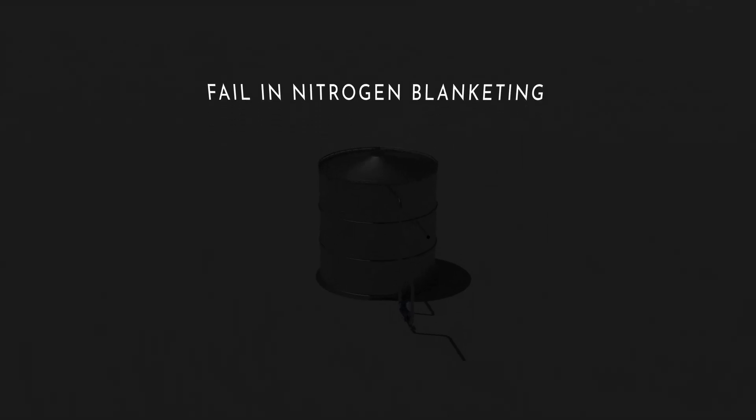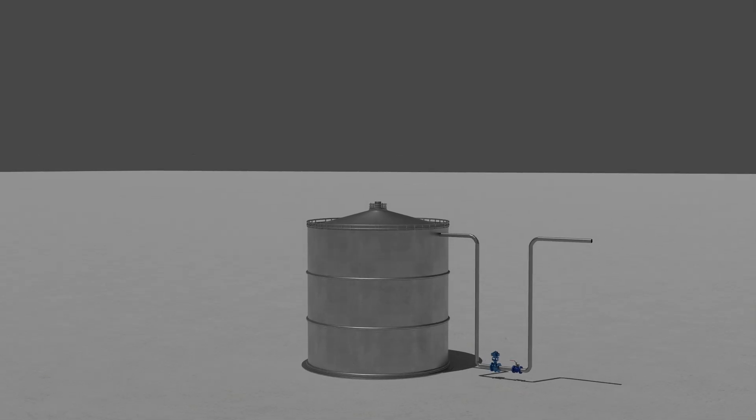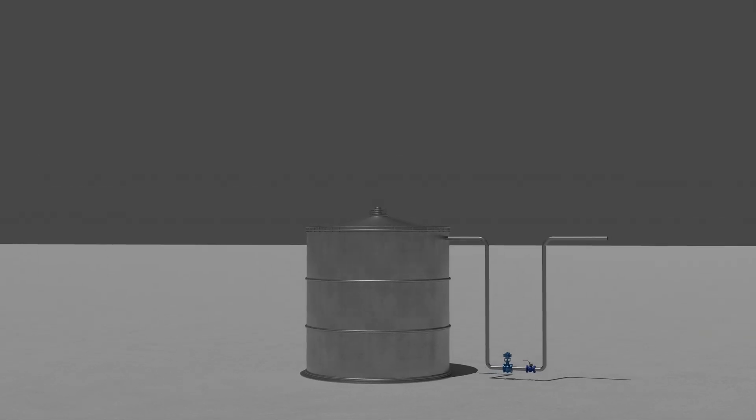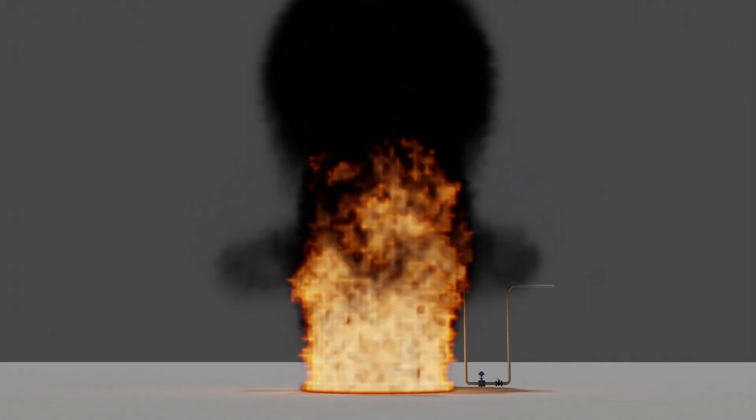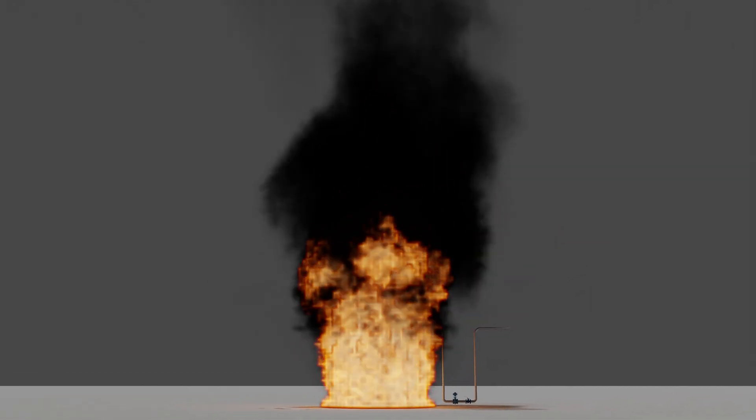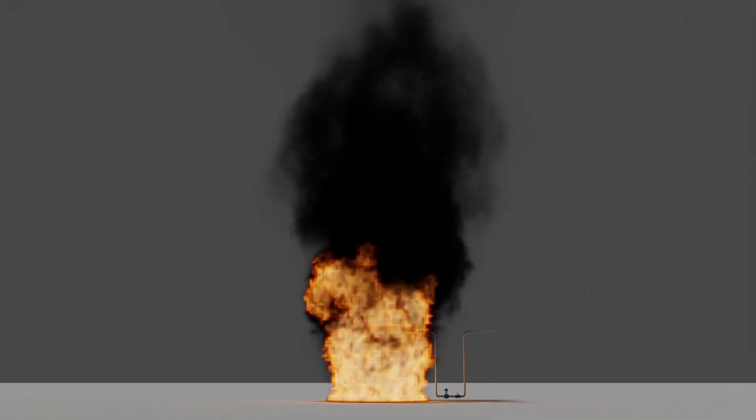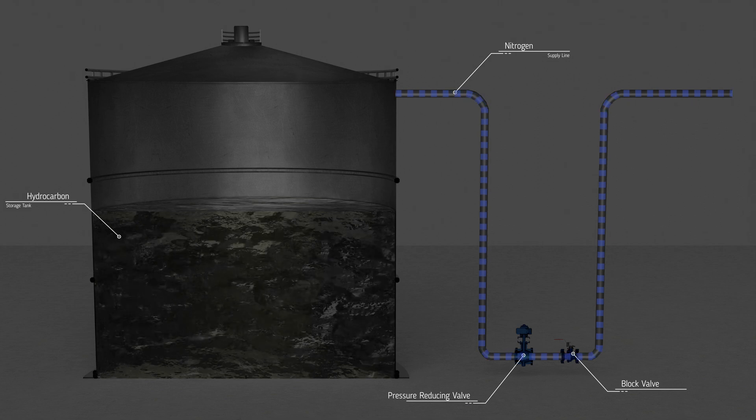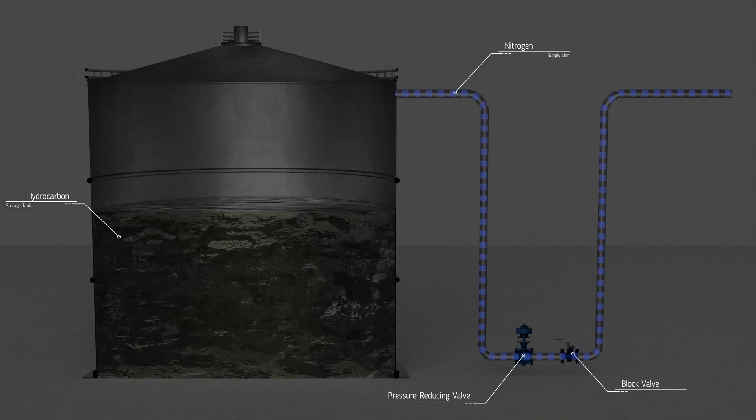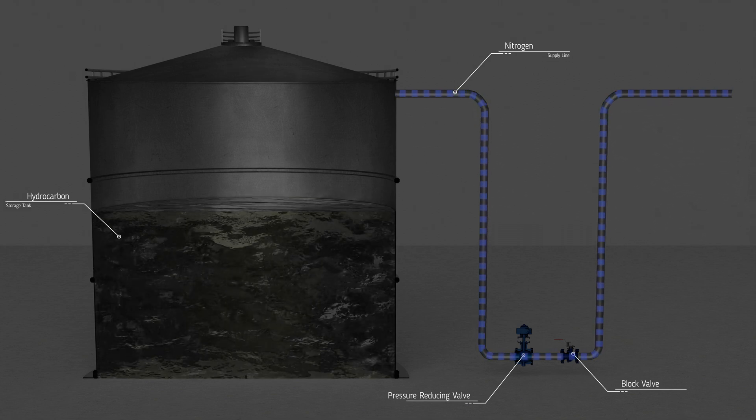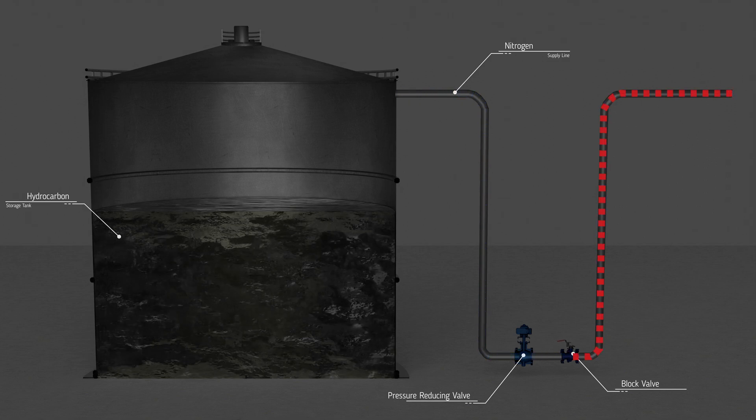Fail in Nitrogen Blanketing. An explosion in fire occurred on a fixed-roof tank filled with hydrocarbon that was supposed to be blanketed with nitrogen. After the explosion, it was found that the nitrogen supply had been isolated.